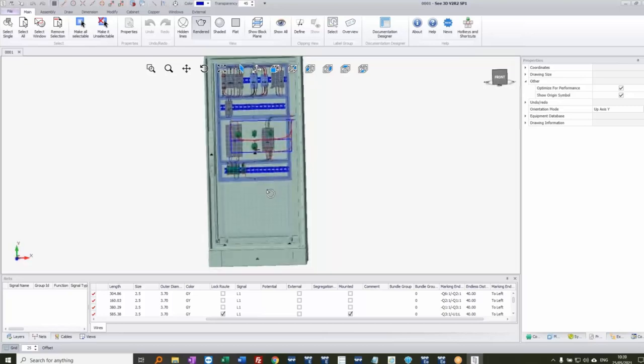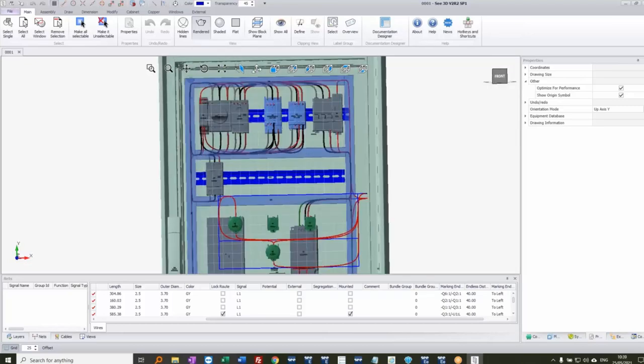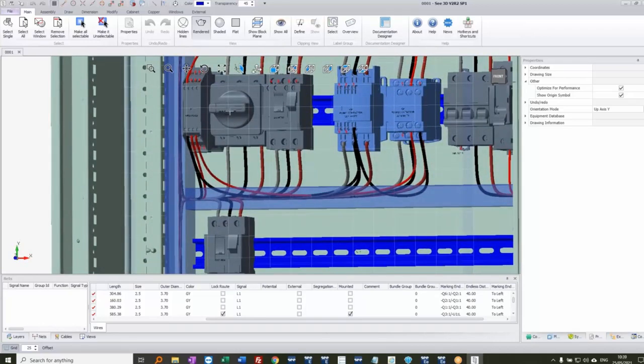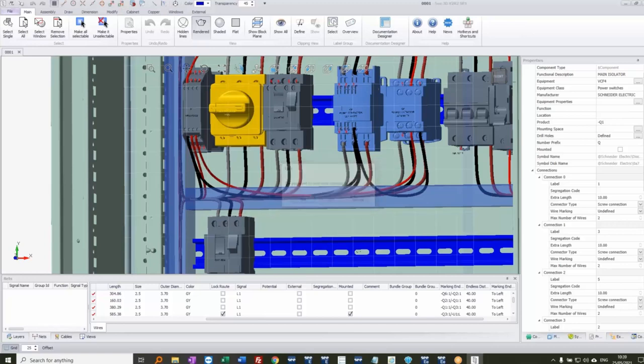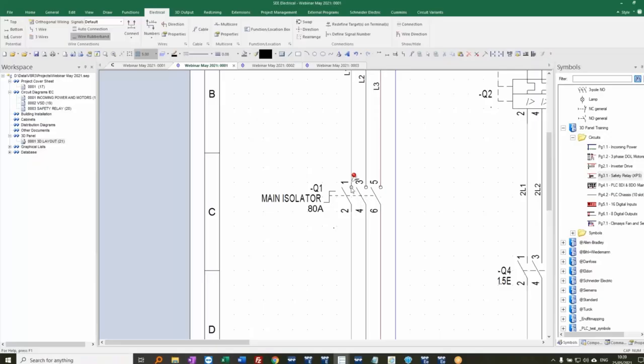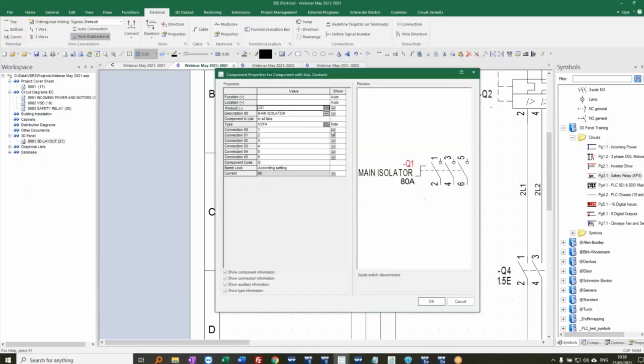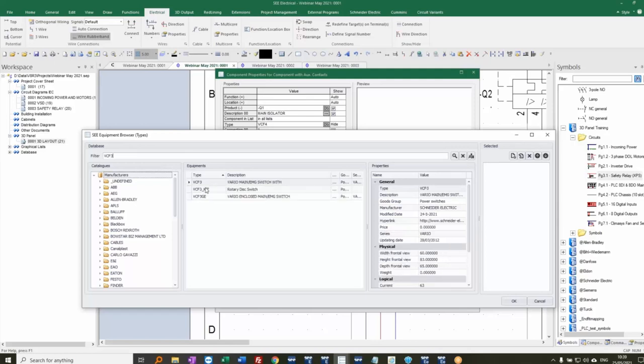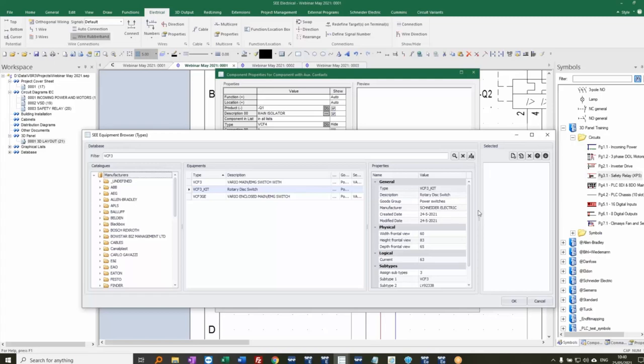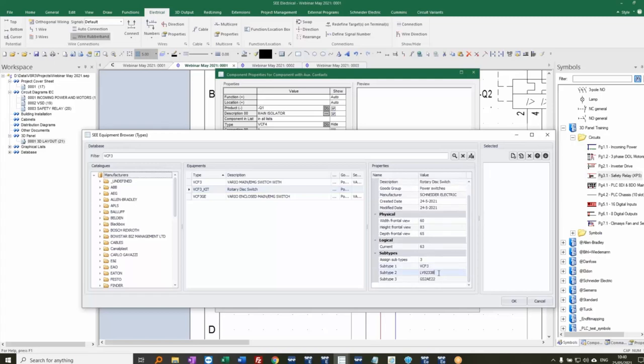A couple of additional things: if we want to change a component — say a different disconnect switch with a door-mounted handle and shaft — I can right-click and say 'Jump to circuit diagram'. Back in the schematic it highlights the component. I double-click it and go to the parts database to search for a different one. I delete the VCF4 and search for a VCF3. There's also a kit available — a disconnect switch together with a handle and shaft — so double-clicking assigns all three parts in one using subtypes.